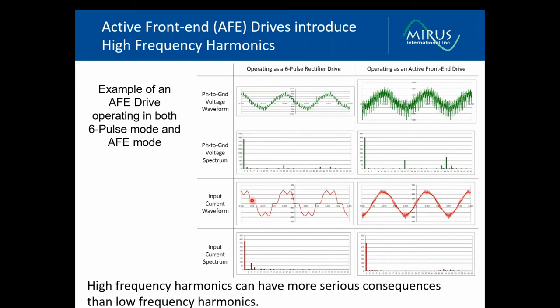Input current distortion, typical of a six-pulse, you're going to see the double pulsed current wave shapes that has predominantly fifth and seventh harmonics as the harmonics that it generates. The AFE looks a bit more sinusoidal, but with a high frequency ripple, lower levels of the low frequency harmonics, but we can see a band peeking out here of the high frequency levels.